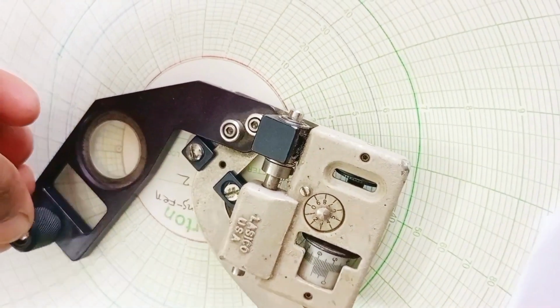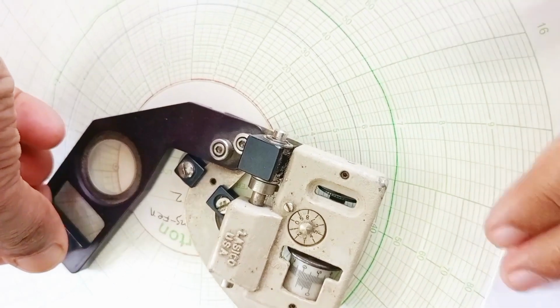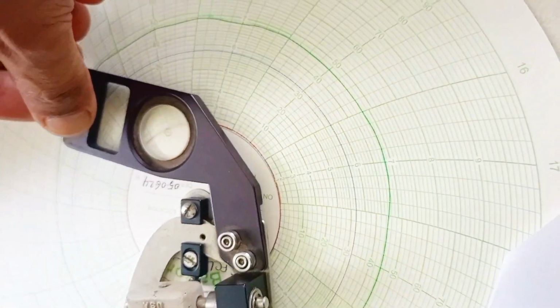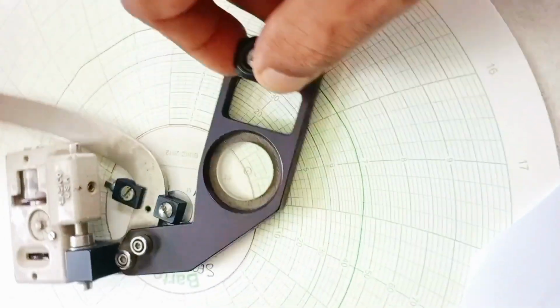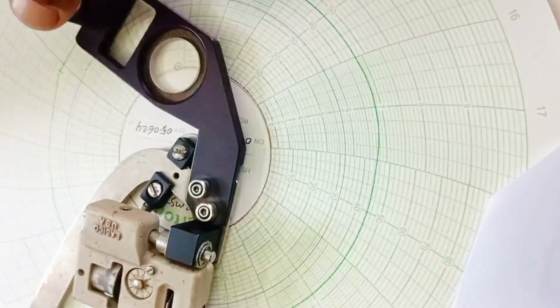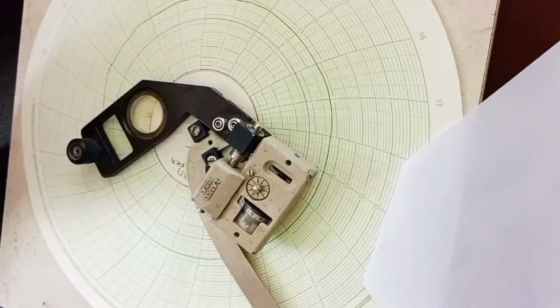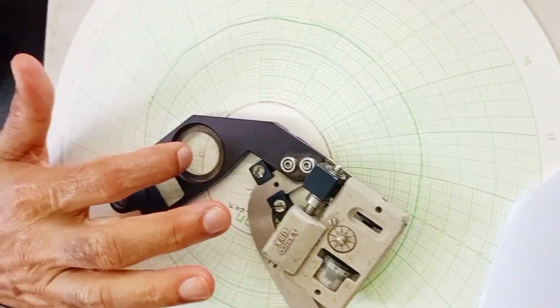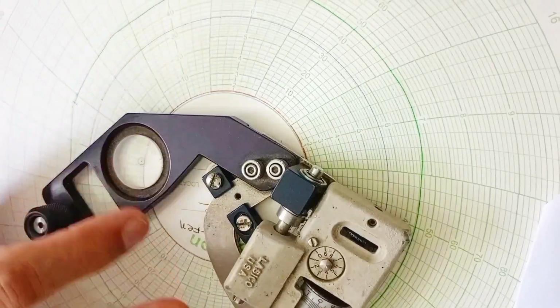Most strip chart recorders use a servo feedback system to ensure that the displacement of the pen across the paper tracks the input voltage in the required frequency range. A potentiometer system is generally used to measure the position of the writing head. The most traditional chart recorders record data on paper.